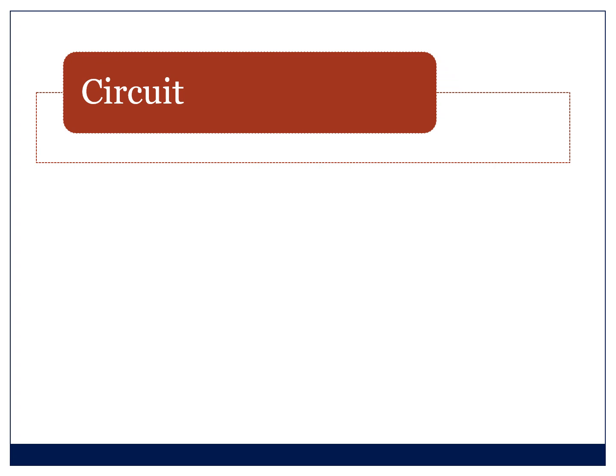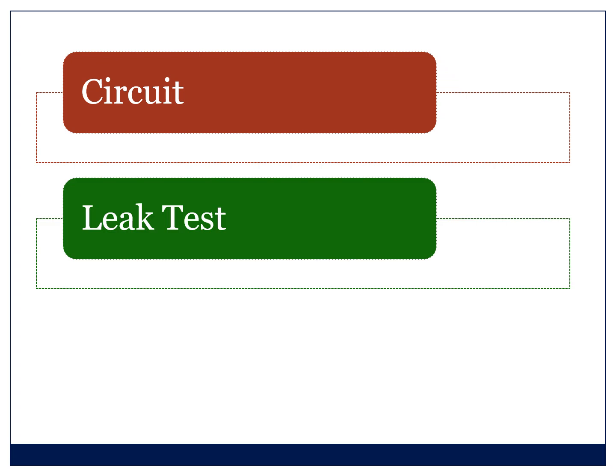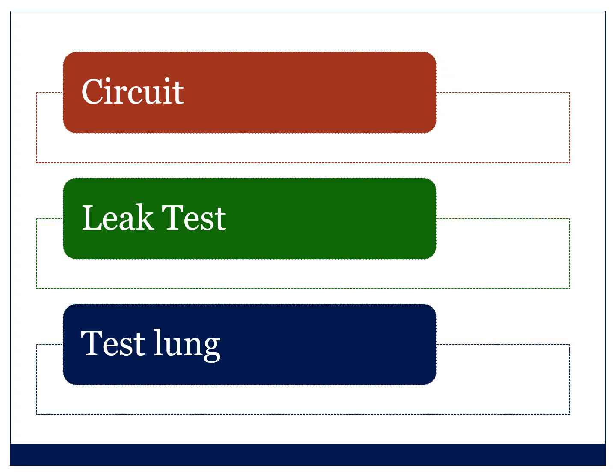The next thing you do is connect the patient's circuit. The circuit should have no holes or cracks in it. It must be connected correctly. It's got a Y-piece and a reservoir bag. You then need to do a leak test, and you put a test lung on and you see that you can ventilate with the circuit.